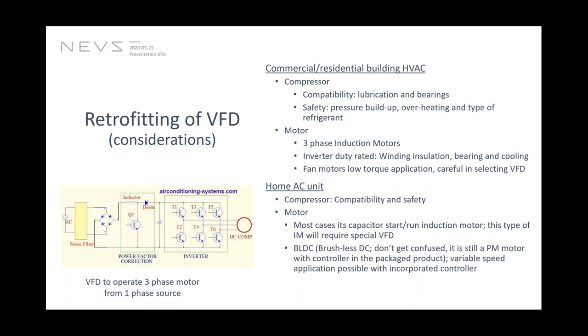with respect to the compatibility with the variable speed application and safety, and with regard to the motor, because it's a single phase application in the home AC unit. So it is possible to implement a VFD with a single phase induction motor. Basically, it's a capacitor start or capacitor run induction motor, which is probably not ideal for a VFD application. But on the other hand, quite a few manufacturers are using BLDC, brushless DC.